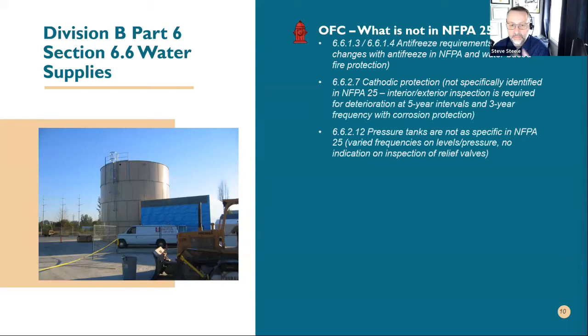But the one that is missing, and like I mentioned before, this is missing on all systems in general, is the need for relief valves. So, where it started with gridded wet pipe systems requiring relief valves to now all wet pipe systems require relief valves, there is no language in 25. So it's a matter of, like I said, it has been identified, or there is discussions requiring from that committee to have specific language on relief valves as well.